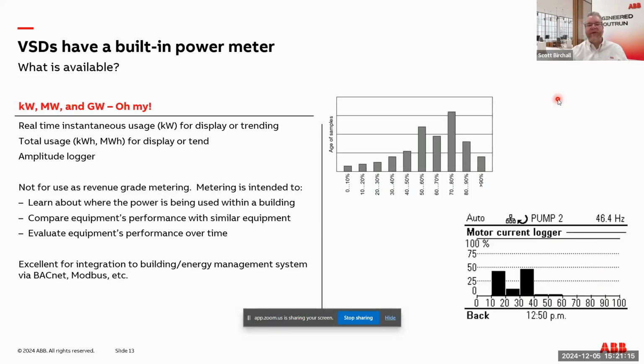So one thing I want to point out with this metering is this is not meant to be revenue grade metering, meaning you're not supposed to bill somebody for it. So if you're a large commercial facility and you want to bill different clients based on an air handler that feeds their floor or their office, the accuracy is not there. So these are going to be better, 5% or better. Revenue grade meters are a lot of times like 0.5% accuracy, just depending on the particular meter and what part of the world you're in. What these meters are really for, though, is learning about what power is being used in the building and where it's being used. So understanding, hey, is my power being used on the air handlers, pumps?